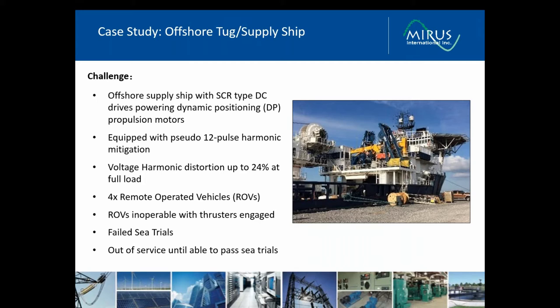The existing harmonic mitigation scheme of phase-shifting transformers operating in parallel with impedance-matched inductors failed to reduce the voltage distortion to acceptable levels. This could have been predicted, as phase-shifting or pseudo-multipulse strategies are not a viable solution for thyristor-based or SCR-based DC drive applications. The notching that's introduced in particular is not canceled by the phase shift. It just gets shifted and actually distorts the currents and voltages even further.